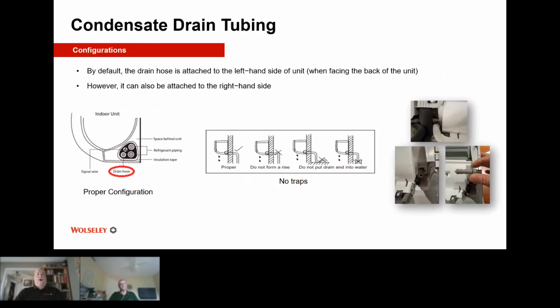Okay, condensate drain tubing. By default, the drain hose is usually on the left-hand side of the unit when you face the unit head on. However, it can be attached to the right. And I believe that most manufacturers today, if you look at the bottom right-hand picture and the bottom left-hand picture, have a plug so that you can take the condensate portion that is provided in the high wall unit and shift it from the left side to the right side depending upon your needs. The most critical thing here is to make sure that you put the plug back in the unused port, because if you don't, you will have condensate coming out of there. So it's key to make sure you put it back in there. It's friction fit. It will come out with normal hand pressure, and it does have a rubber O-ring to seal so that it won't come out.